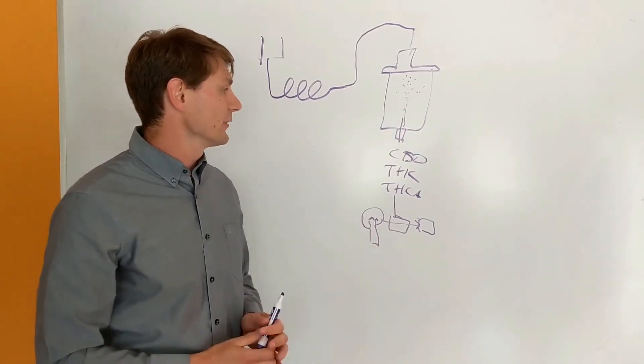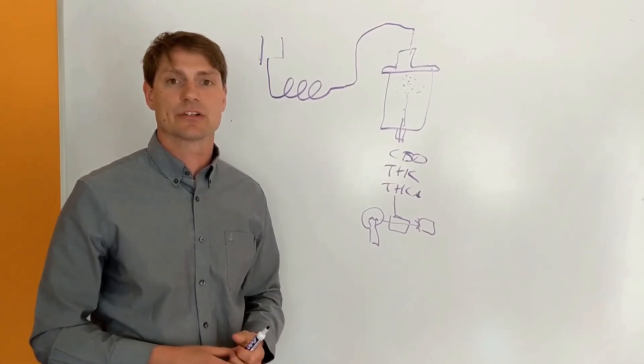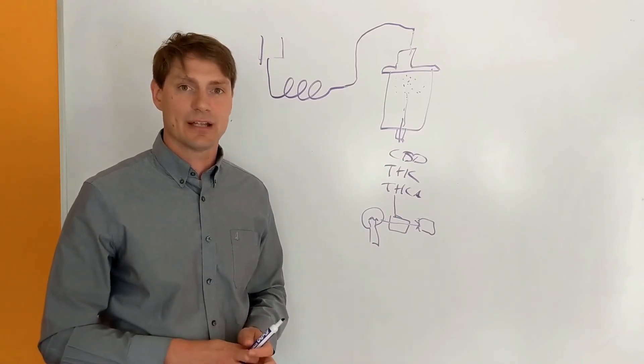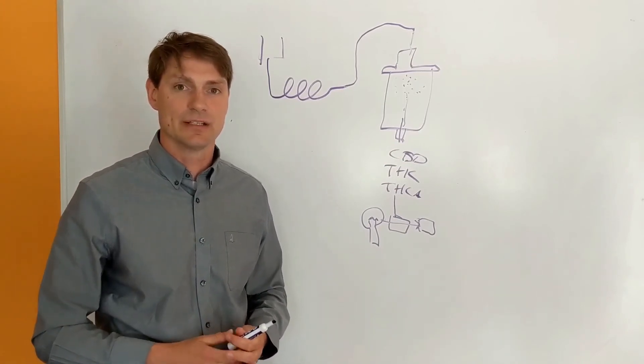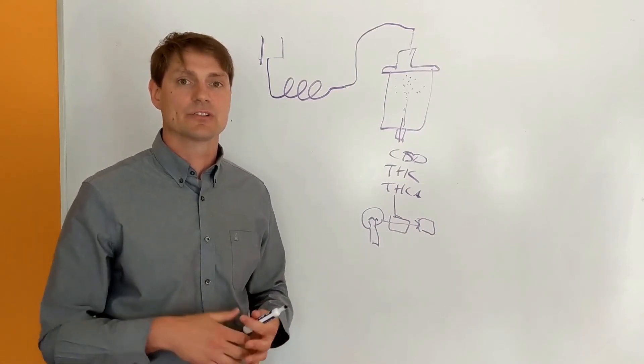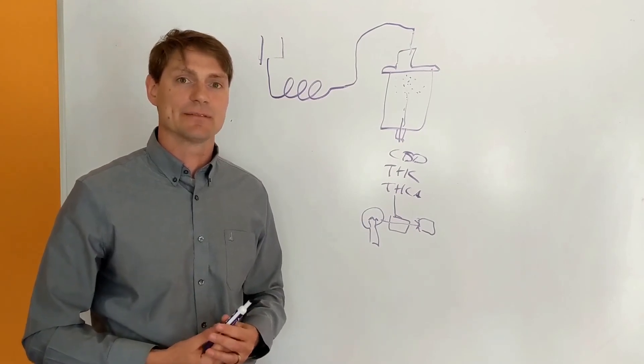One thing to note, though, is that our system is calibrated directly with calibration standards. So there's no lookup library or anything like that going on. So the device is actually calibrated very similar to an HPLC would be, which is using analytical standards that are injected into the device during calibration. This is something that happens at the factory, so you don't have to worry about it.